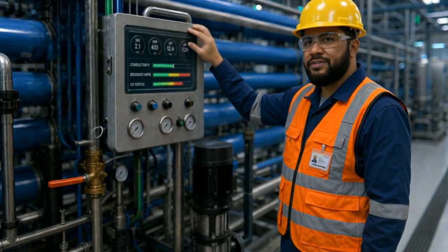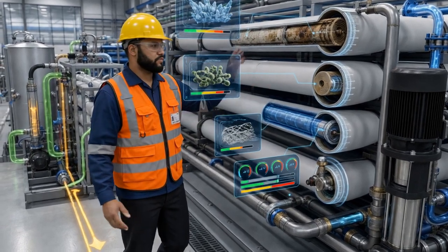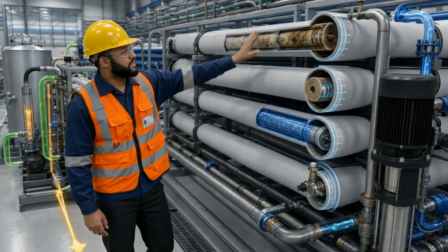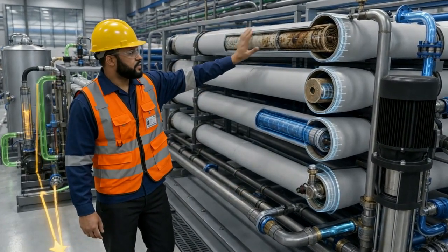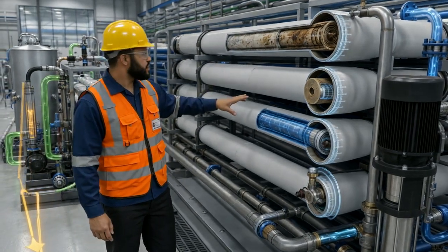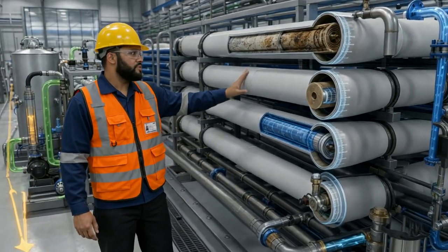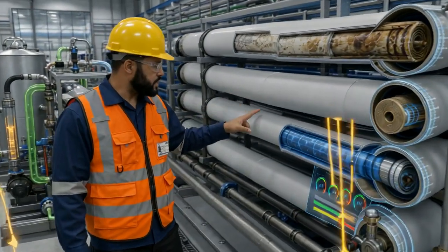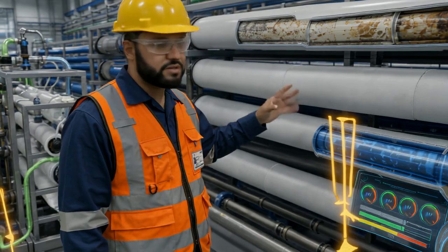alarms become failures. Even with good pretreatment, RO plants face 3 major operational challenges during daily service. The first is scaling. This happens when minerals such as calcium carbonate, calcium sulfate, or silica exceed solubility limits and form hard deposits on the membrane surface. Correct antiscalant dosing, proper pH control, and realistic recovery settings are vital.